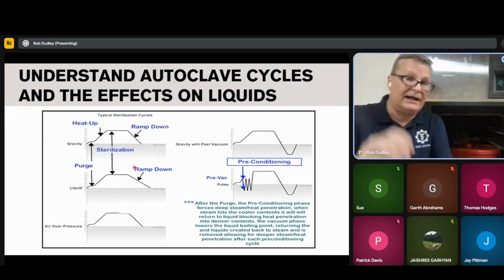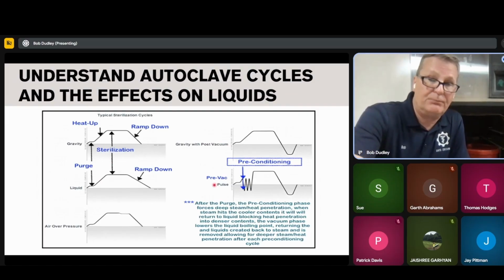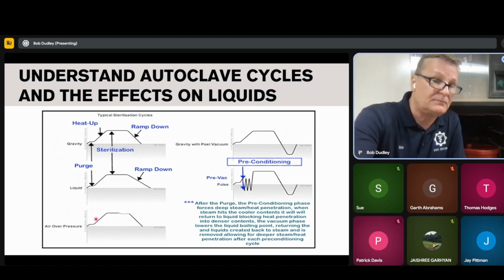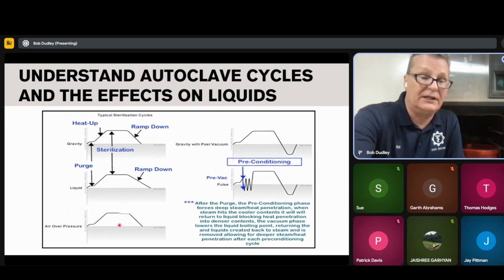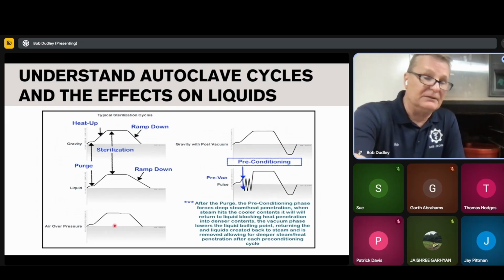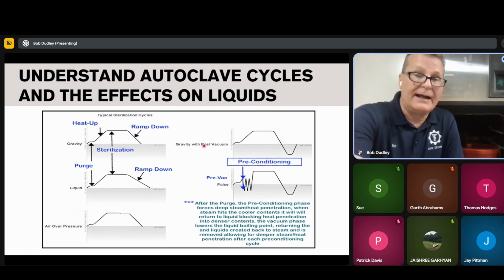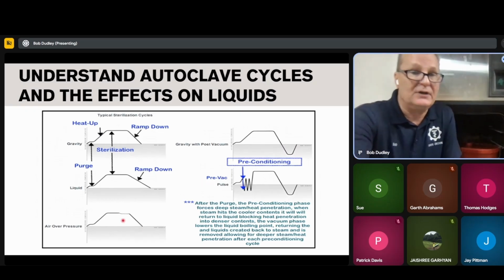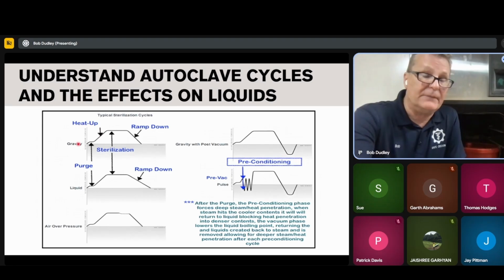So let's go and have a discussion about what happens. Now, I put this chart up here because it had pretty much every cycle. We're going to ignore the air over pressure. These cycles generally run in bulk sterilizers. They're used for a specific reason. The air over, they use a purified air to inject. Gravity with post vacuum, I don't worry about that because most of you guys are not using that so much anyways. I'm going to talk about the three major ones: the gravity, the liquid, and the pre-vac.